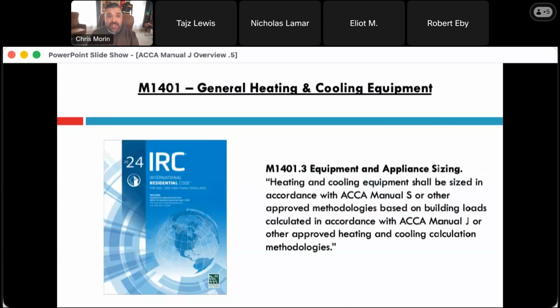is code. So in your 2024 IRC, that's the residential code in Austin and throughout the country, and this goes way back to like 2015's version. It's the same code reference, 1401.3. Heating and cooling equipment shall be sized in accordance with ACCA Manual S or other approved methodologies based on building loads calculated in accordance with ACCA Manual J or other approved heating and cooling methodologies.